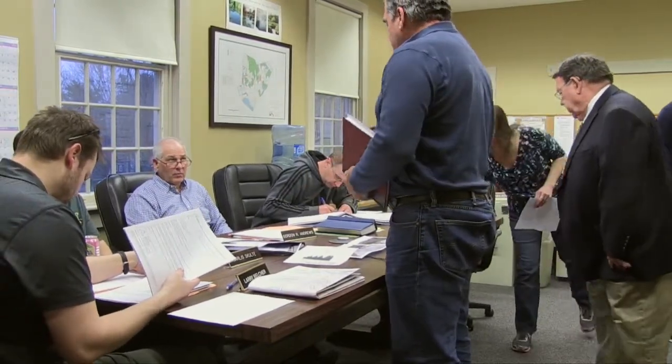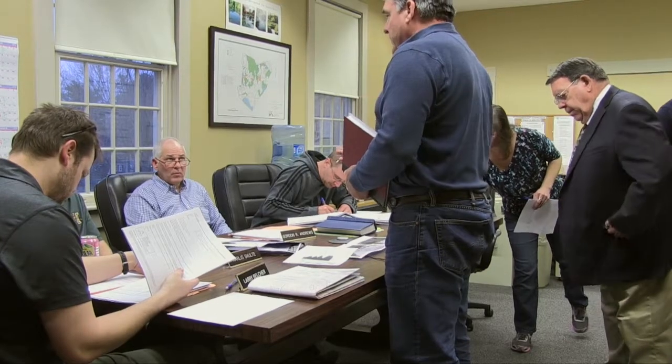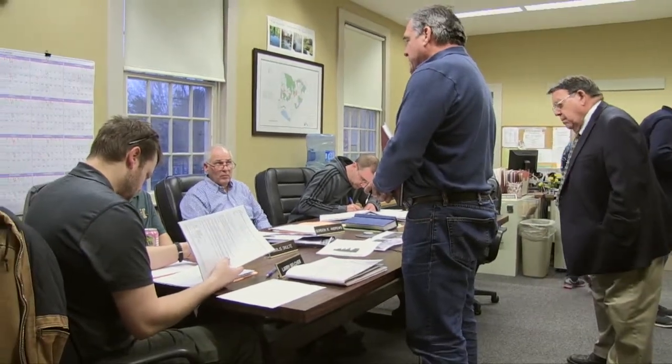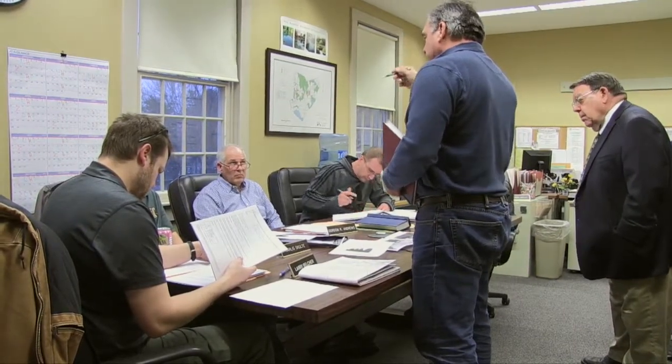One question, are you making a deal with the provider on who you're going to use and how you're going to hook up ultimately? Right now we're in the system impact study. National Grid's it's their service territory, so that's who we hook up with. Right now they're studying how they're going to have to build out their infrastructure in order to connect with us. They're going to have to bring the 3-phase, right now it's single phase coming down Pratt. We're just going to have to bolster that and turn it into a 3-phase, probably replace the whole thing with a 3-phase wire gang as opposed to just a single wire.